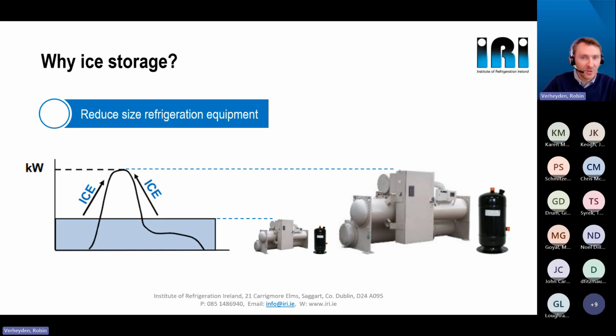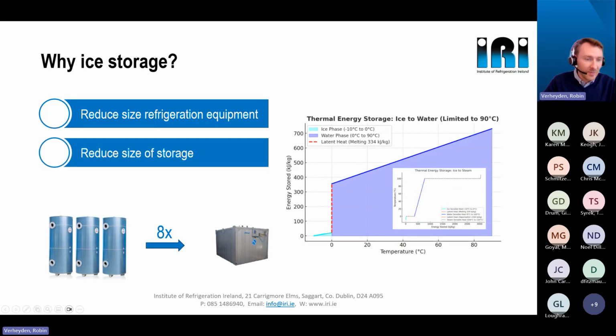But there are more benefits. Ice thermal storage is also a very efficient way to store energy or cooling, because it utilizes latent heat. The graph shows that the amount of energy required for a phase change per kilogram of water is quite high — compare the red line with the blue line, representing the delta T needed for water to store the same amount of energy as with latent heat. As a result, the storage volume with ice can be up to 8 times smaller compared to water storage.